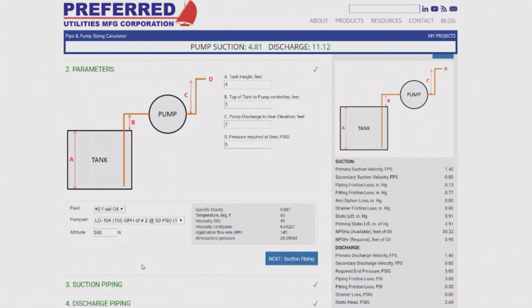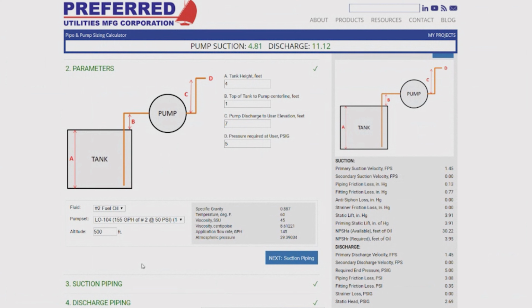And David, if I could, just for some of the folks here in the Northeast, the calculations that you're describing here, doing the double check for the return pump, this is typically going to be for a system where everything is basically at the same elevation for the most part. We're not talking a high rise, but is spread out quite a bit. So an application like you would see in Texas. The systems we have in Texas tend to be single level. So our pumps, our generators, and our tanks are all going to be at the same level, usually.